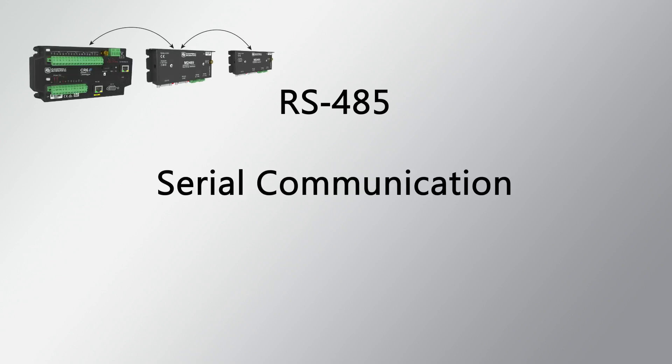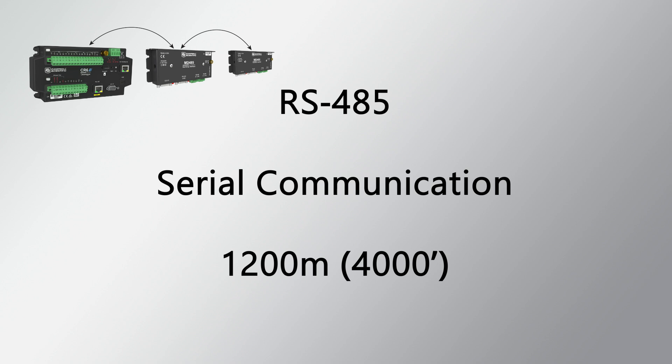A common place for ground loops to occur is RS-485 communication networks. RS-485 is a serial communication protocol designed for distances of up to 1,200 meters. Over such large distances, differences in reference potential can arise, leading to ground loops.